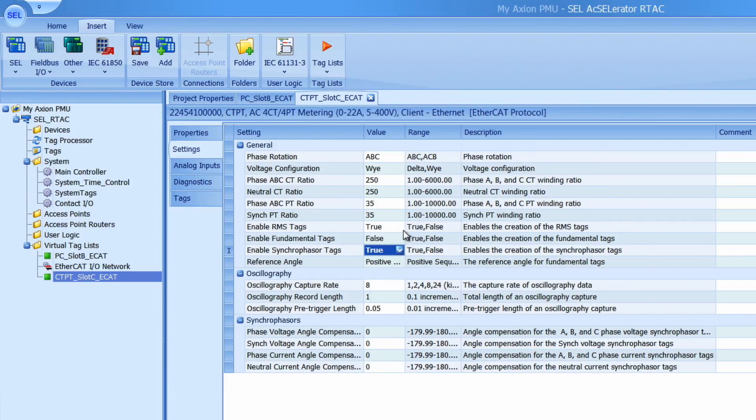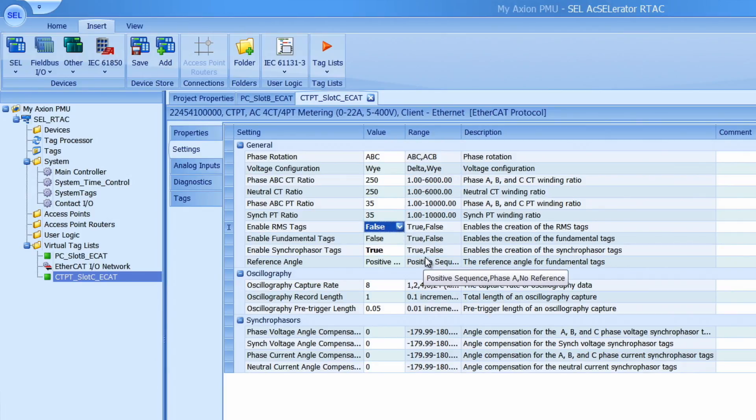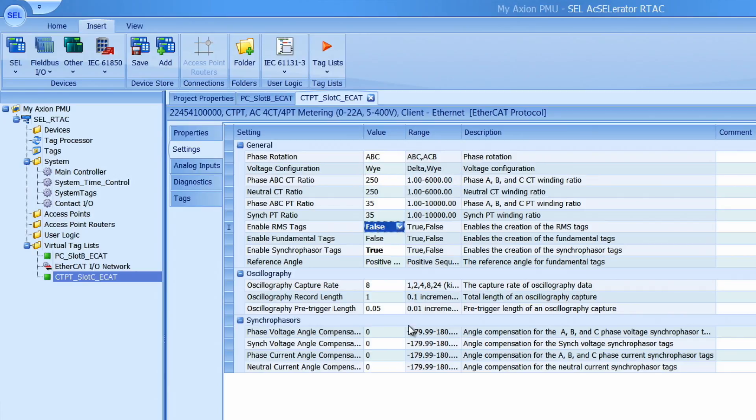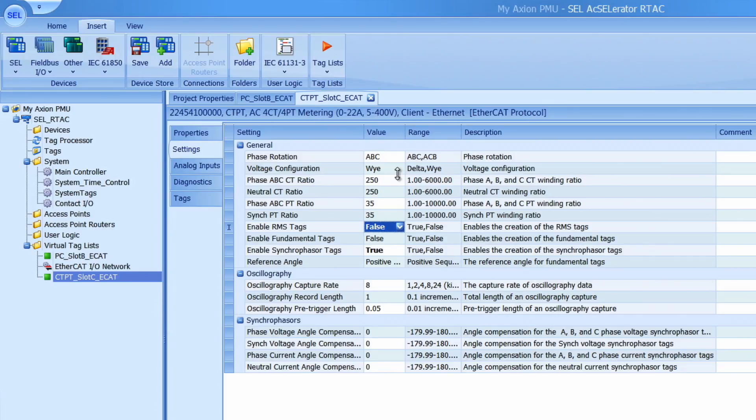In this case I don't want to use RMS tags so I'm just going to disable that one because that one's enabled by default. And I'm not going to touch any of these other settings but make sure for your application you set the ABC CT ratios, the phase rotation, all these other settings correctly for your application.